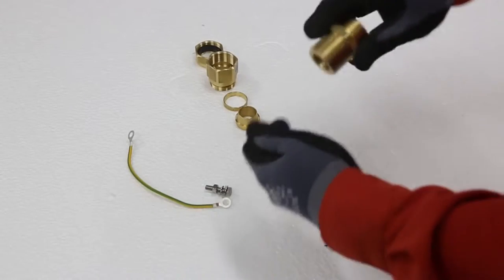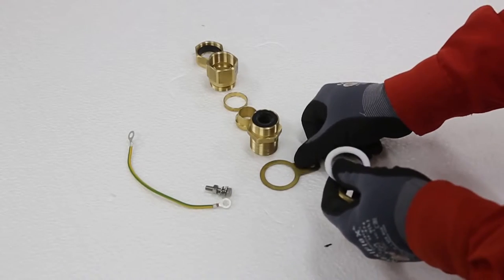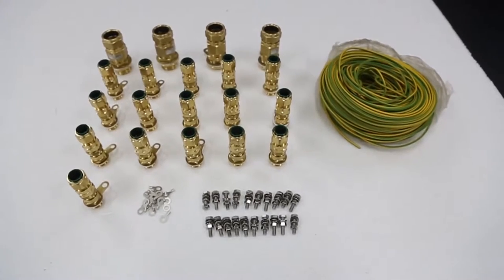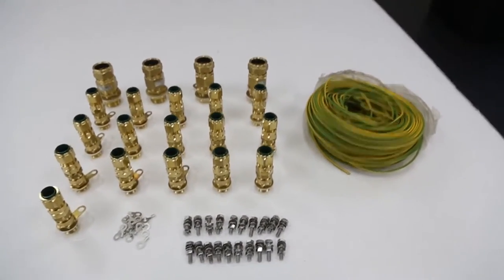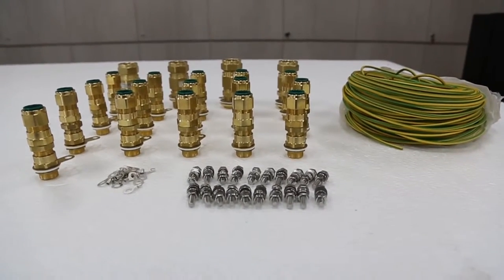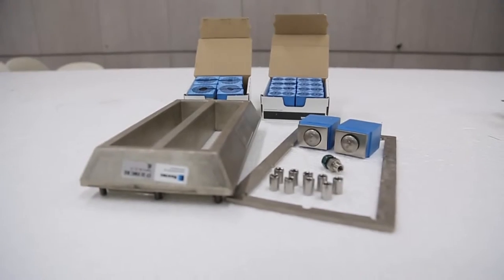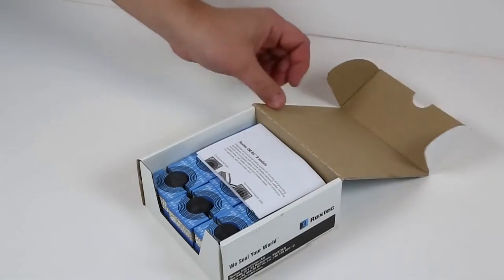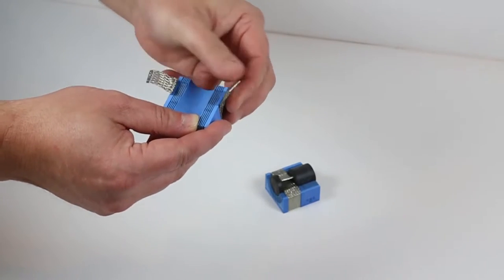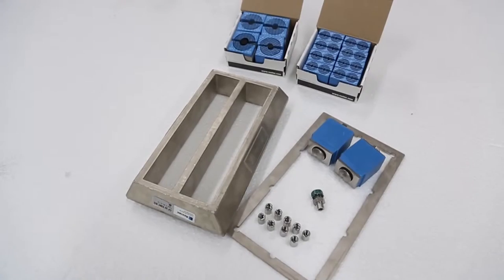Here are the parts required for a complete installation. Each cable gland consists of 11 components, which makes a total of 220 components, plus 20 screws, 20 ground lugs, and the earth cable roll. A Roxtec BG seal consists of a frame, a counter frame, a couple of adaptable BG sealing modules, including a conductive braid and two compression units, plus one screw and nine bolts.